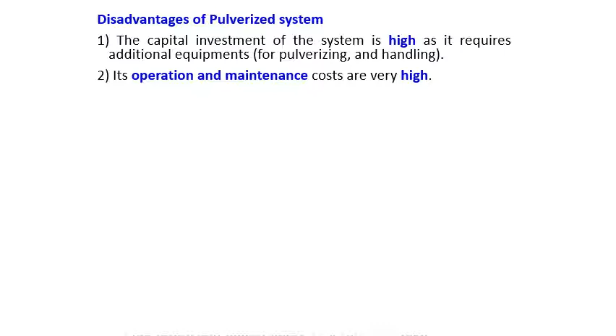Usually combustion is smokeless. The disadvantages of the pulverized system are: the capital cost, meaning the initial cost, will be very high. The operation and maintenance costs are also very high, because though as told an ash handling system is not required, electrostatic precipitators are required. That's why its cost will be high. And there are chances of explosion, because it will behave like a liquid, and a liquid fuel is more dangerous than a solid fuel. Gaseous fuel is much more dangerous than solid fuel.